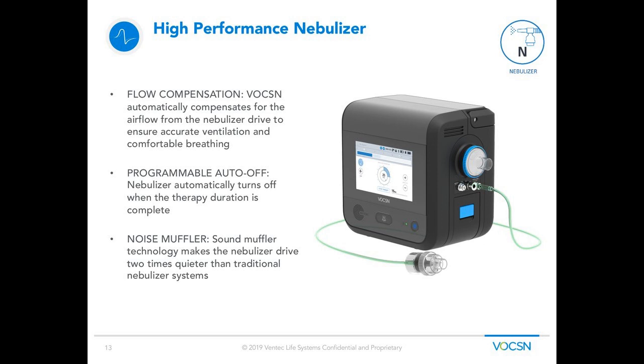Oftentimes the ventilator alarms the entire time, getting high pressure alarms because the two separate systems can't sync with each other. We talked about the benefits of integration: with one device, the ventilator can compensate for the additional flow from the nebulizer, making it a much more comfortable experience for the patient. You can also set an auto timer, so after 10 or 15 minutes the nebulizer automatically turns off and ventilation resumes in the background, without the caregiver needing to come back and hit stop.